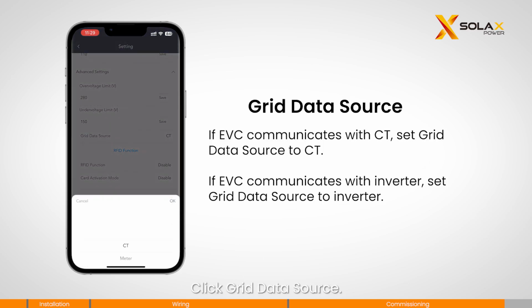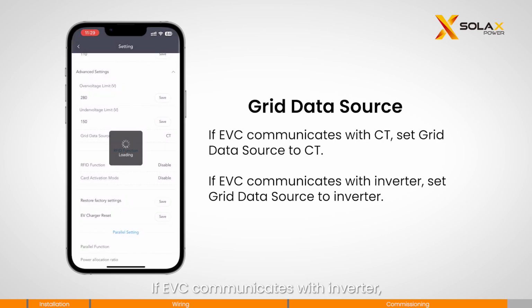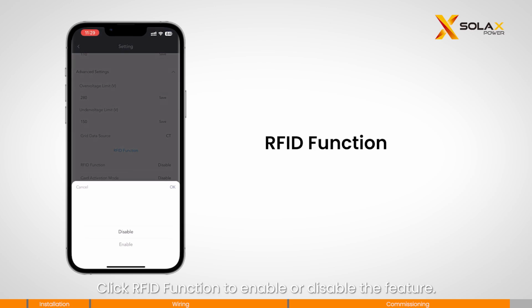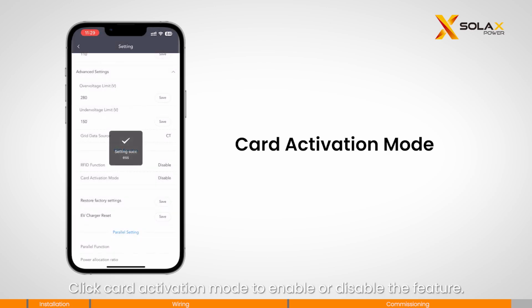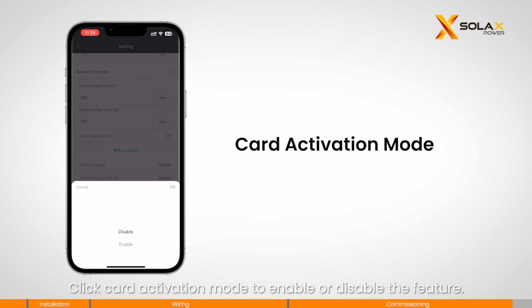Click Grid Data Source. If EVC communicates with CT, set Grid Data Source to CT. If EVC communicates with Inverter, set Grid Data Source to Inverter. Click RFID function to enable or disable the feature. Click Card Activation Mode to enable or disable the feature.